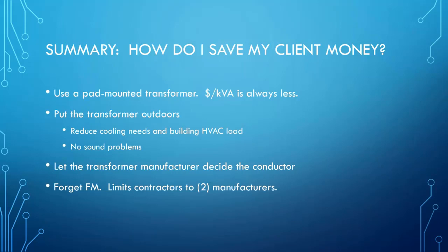The next thing I would do is let the transformer manufacturer decide on the conductor. I would specify transformer shall meet DOE 2016 efficiency requirements and leave it at that. Now you're forcing a transformer manufacturer, as the contractor goes out for bids, to provide the best transformer at the best price, regardless of conductor.